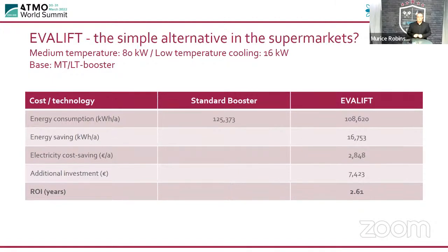So having a look at a medium system, so 80 kilowatts and 16 kilowatts low temperature, the standard booster used 125,373. And with EVALIFT, 108,620. So you can see as the kilowatts increase, the return on investment starts coming down, because you can see here the investment was only 7,423. So we're saving 2,848. So we've only got a 2.5 year payback period.